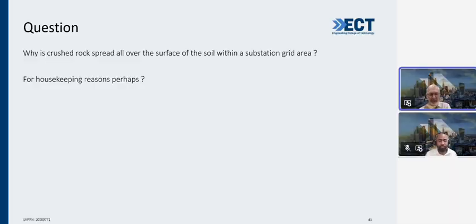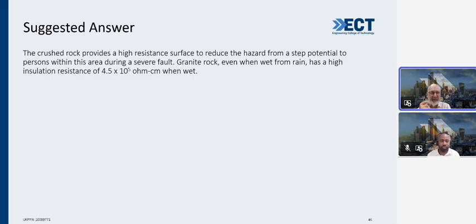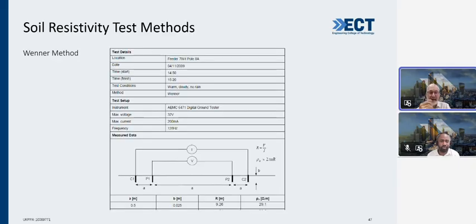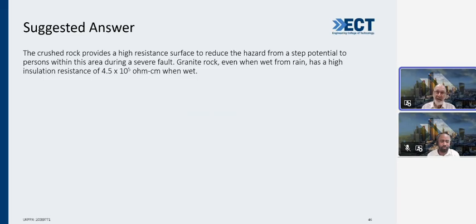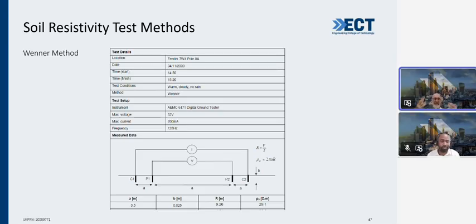Avoid direct contact with earth, but it's high impedance - that's really important. So crushed rock provides high resistance, or impedance is probably the better word, to reduce the hazard from a step potential. Granite rock, funnily enough, even when it's wet, still has a fairly high impedance. That's why, if you've got rocky ground and you're trying to put an earth rod in, it's very hard to get a good result.